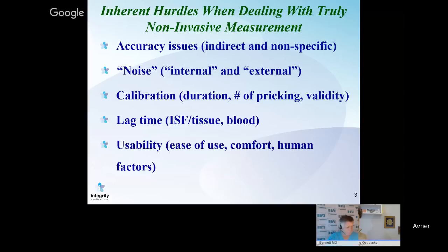Another issue, because of the indirect measurement, is the lag time, which, by the way, also occurs in continuous monitors that measure the interstitial fluid rather than the blood itself. So there is some lag time, which also contributes to accuracy.